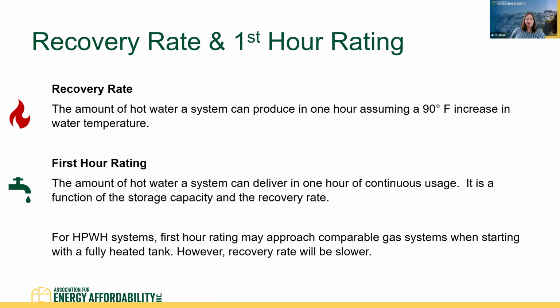Longer recovery rates. The other definition is first hour rating. First hour rating is the amount of hot water a system can deliver in 1 hour of continuous usage, and it's a function of the storage capacity and the recovery rate. So starting with a fully heated tank, how much hot water can be delivered in the first hour? With heat pump water heating systems, the first hour rating may actually approach a comparable gas system. But again, this is starting with a fully heated tank. However, with that slower recovery rate, it's not going to be able to deliver the same volume hour after hour. So that's definitely something to consider and design around.